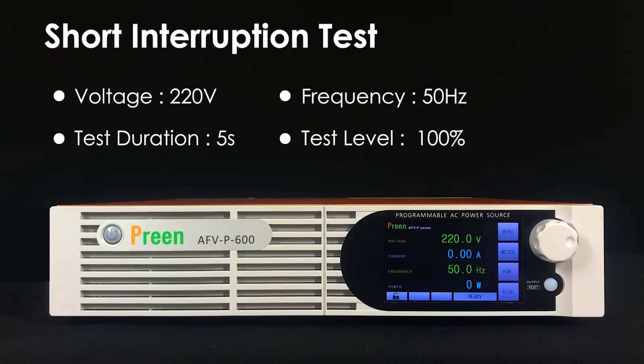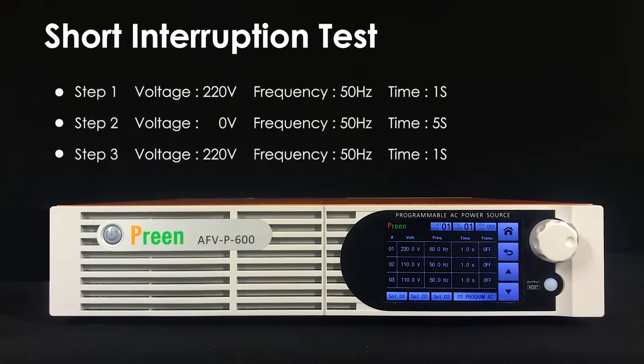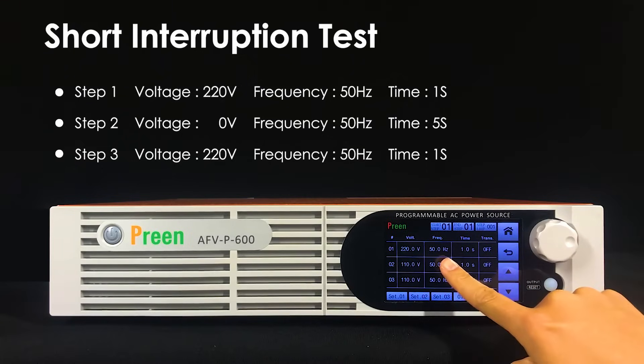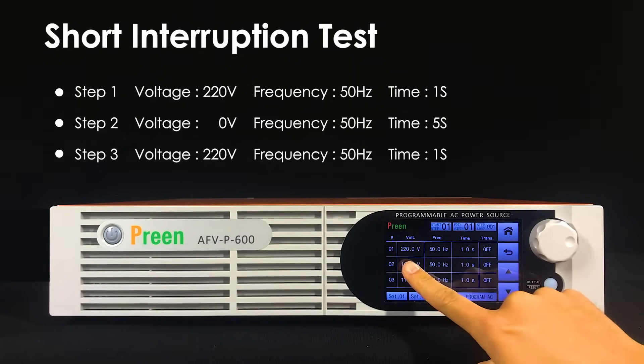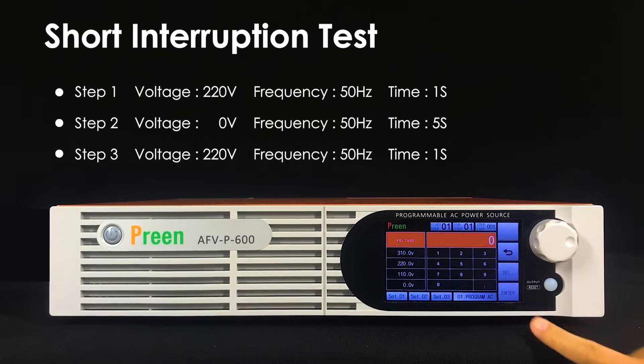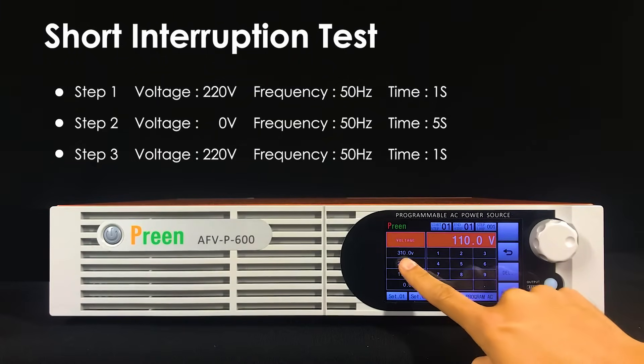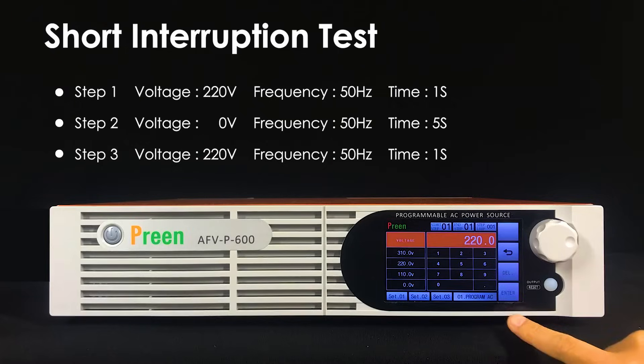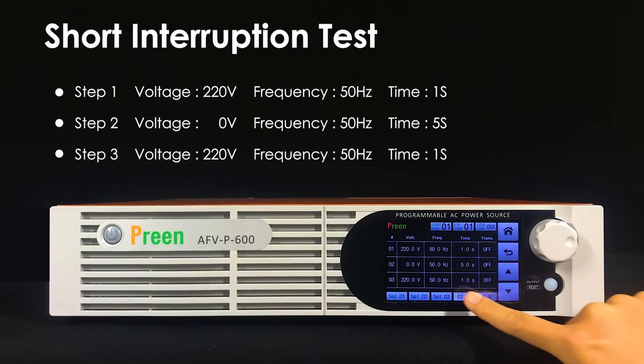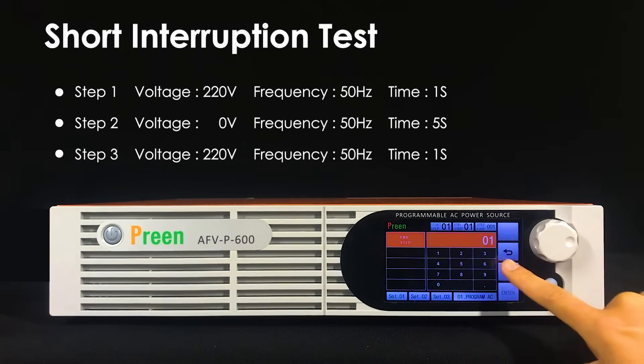For short interruption under nominal 220 volts and 50 hertz, we can use the step feature to simulate. Let's suppose the voltage drops to 0 for 5 seconds. We will set each step's voltage, frequency, and time according to the numbers shown on the video. Verify and set the start and end steps to complete the setting.